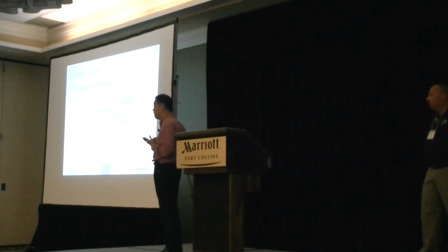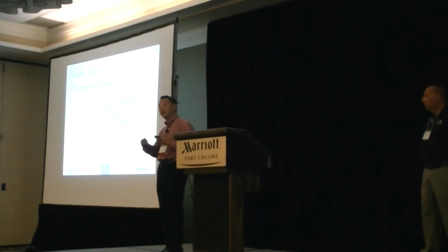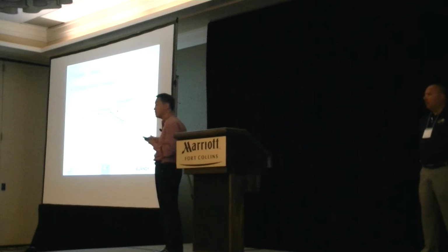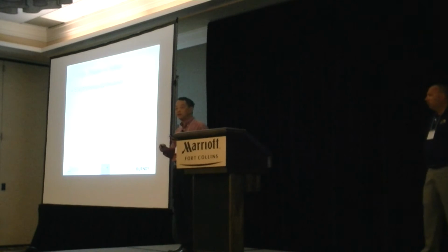And I think the reason it exceeded is because there's some factor of safety built into the Burndy charts. And if you look at the way we did it, we actually did an ultimate strength design where we just took it to failure. So this gave us confidence that we could use the Burndy charts in our TRTB project. And as I indicated earlier, when we looked at the results, a lot of the failures that we had were on the compression side.